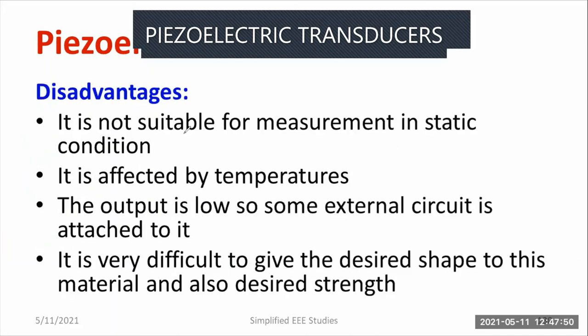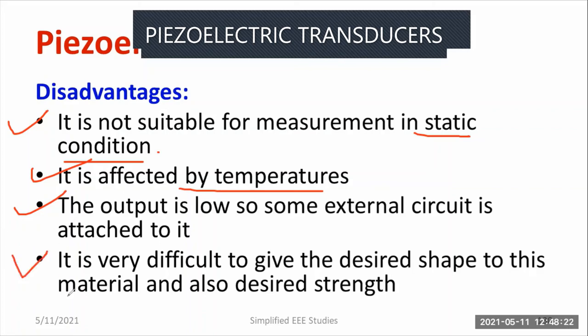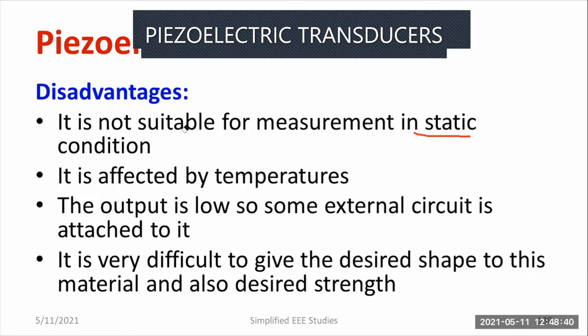What are the major drawbacks of piezoelectric transducer? It is not suitable for measurement of static conditions — only suitable for measurement in dynamic conditions. Temperature effects change the reading. The output is low, so an external circuit is attached for amplification. The output generated from the piezoelectric transducer is very small, and to extract the signal, we require a special type of amplifier that is expensive. Maintenance of that amplifier auxiliary circuit is quite expensive. It is very difficult to give the desired shape and desired strength to the material, and deformation matters a lot in the case of piezoelectric transducer — everything is somewhat complex. These are the few things you have to remember regarding the pros and cons of the piezoelectric transducer.